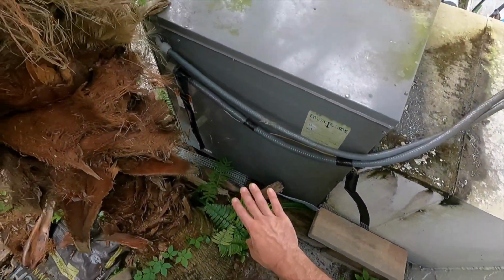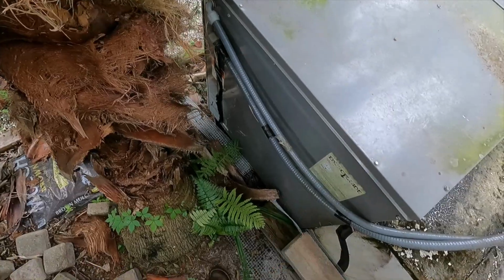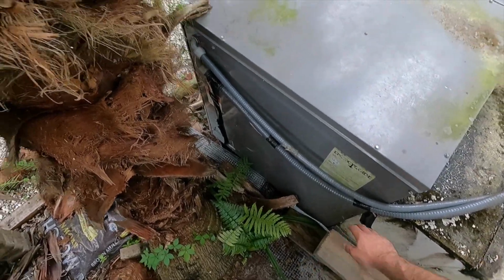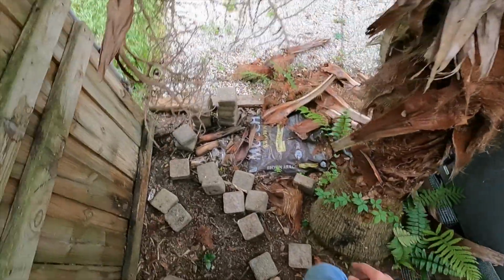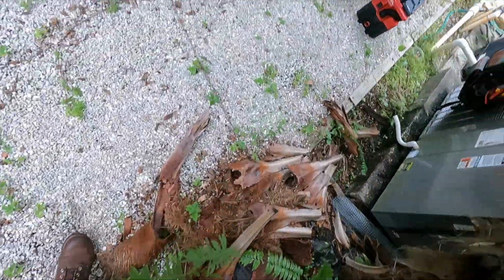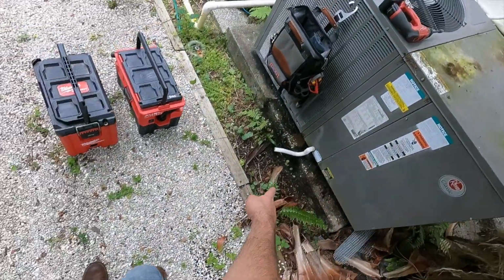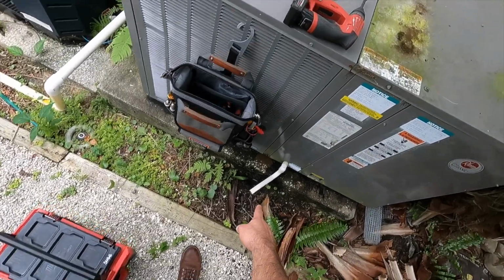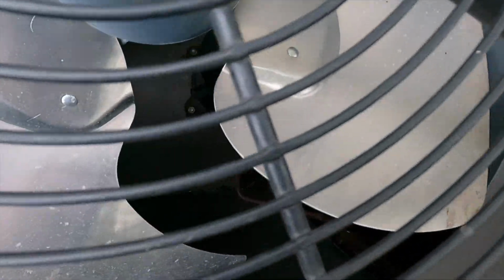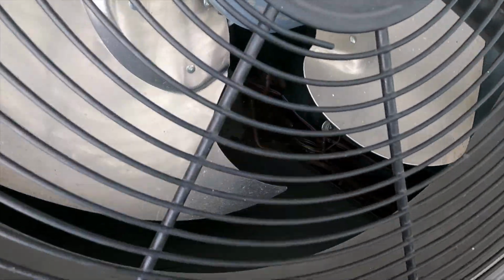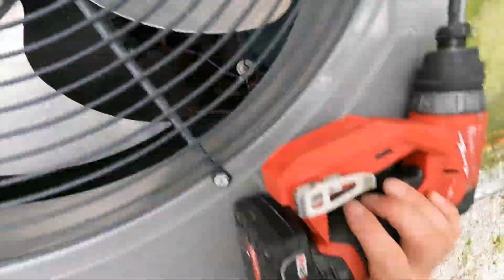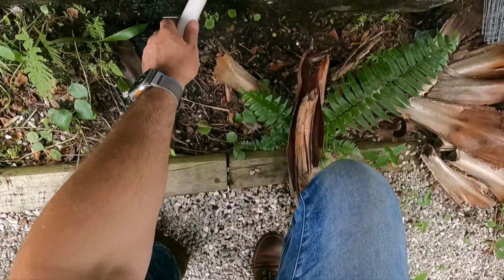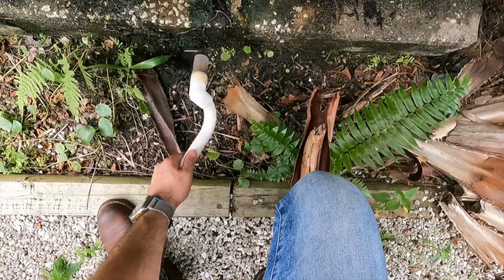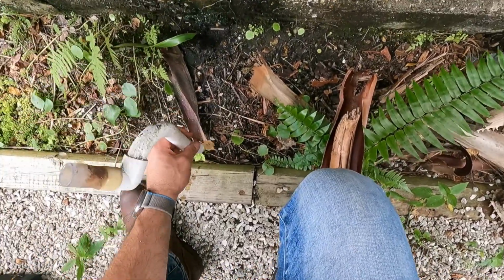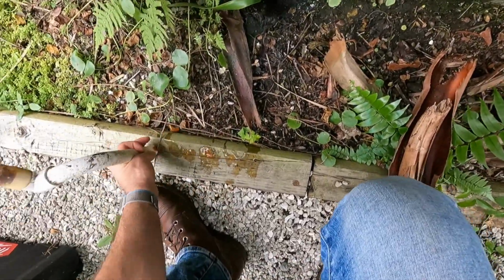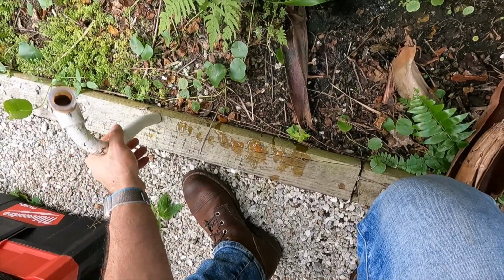All of our electrical equipment and everything's going to be on this side here. Well, nope, actually no. So that's where all the wiring happened, but I believe I can access it from the front. So yeah, electrical panel in the front here, drain line, evaporator coil. I got some water leaking out of the cabinet there, so I bet that thing's clogged up. Oh yeah, you can see water down in there under the pan. It looks like it's clogged, so I bet if I take this thing off here, oh yeah, look at that. Oh yeah, look at that nice stuff.